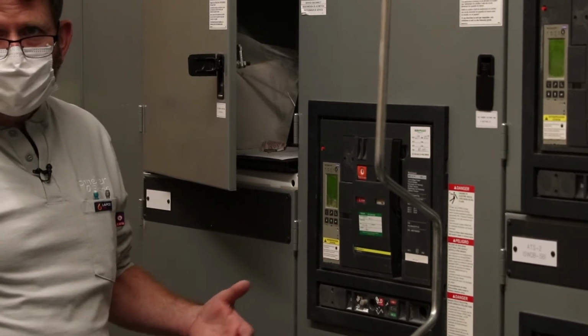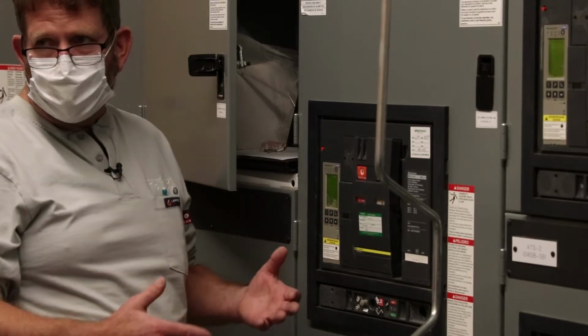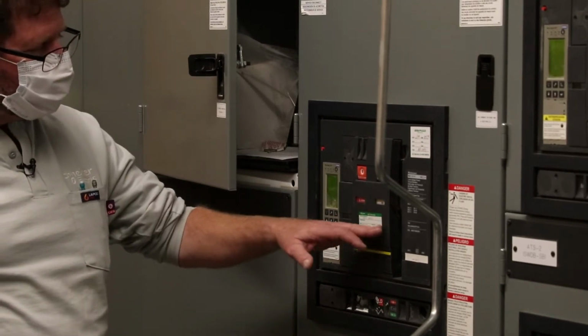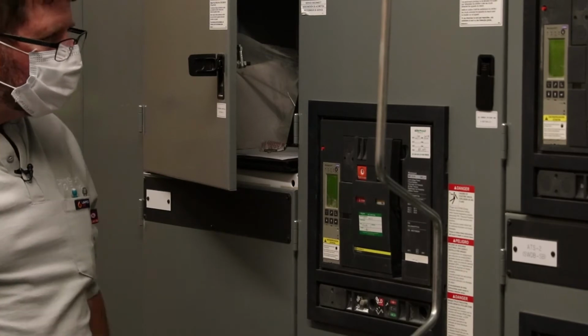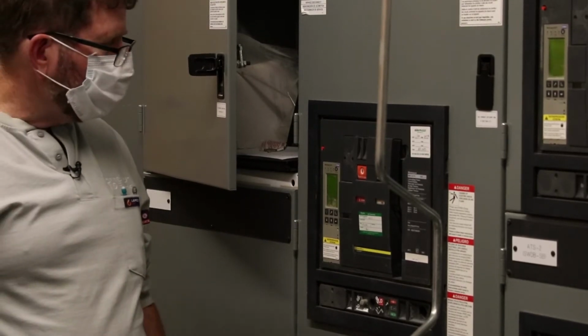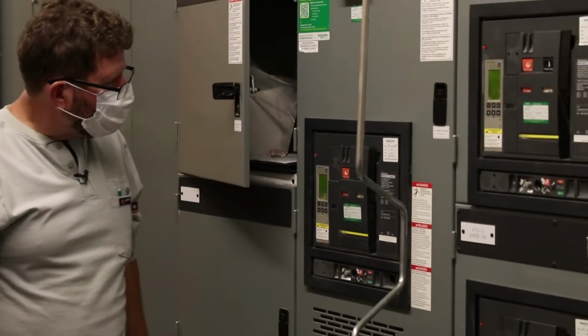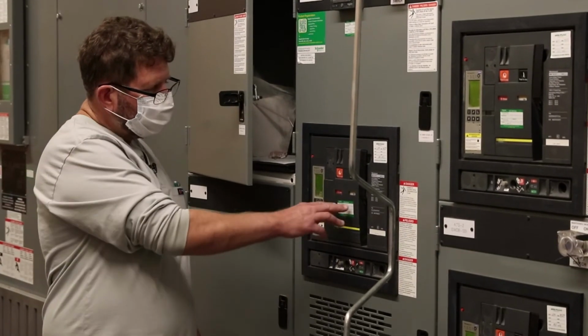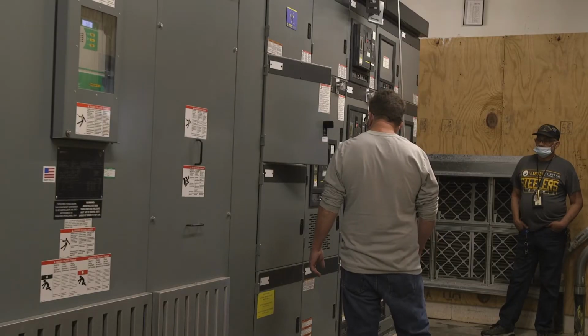There's been some concern, I've gotten concerned calls over the years that my breaker says it's not okay. It's not that the breaker's not okay, it's just not okay to close. If the springs are charged and the breaker's closed, it's not okay to close, because it is already closed. There's a few other things that can drive that.